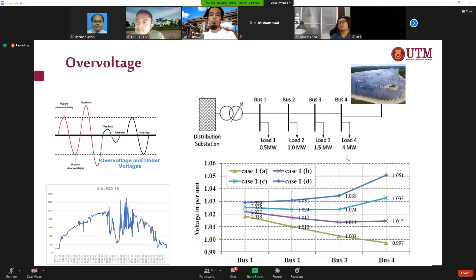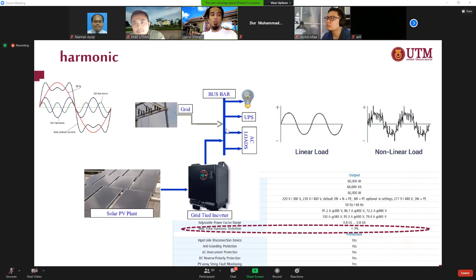It's less than 3%, but the combination of this 3% might cause a big problem on the overall system. We might have an unbalance, especially when you have a three-phase system and you only inject single-phase PV to your network.